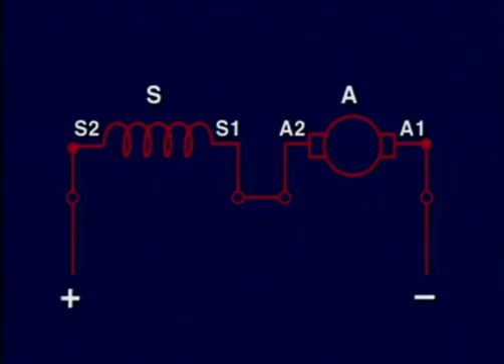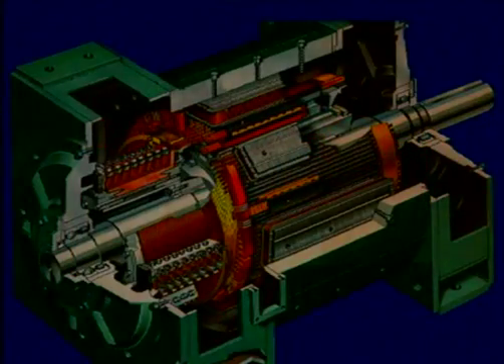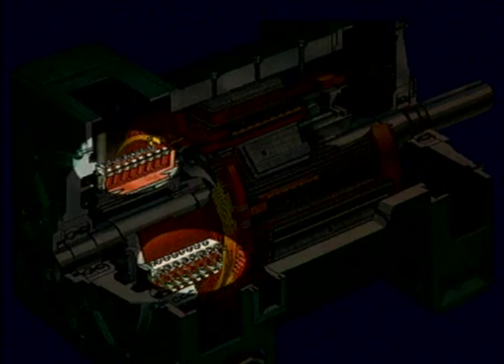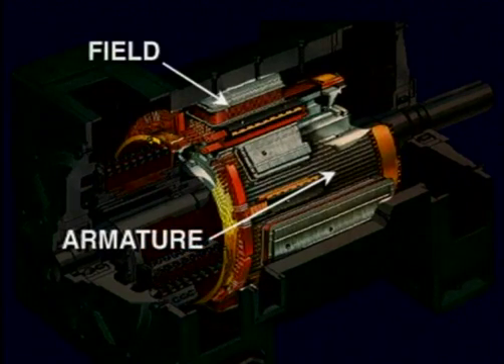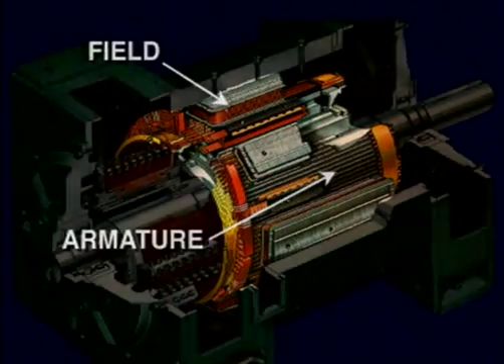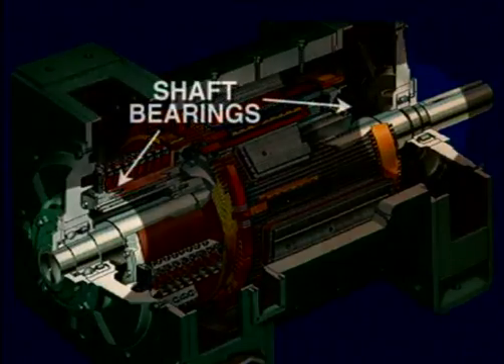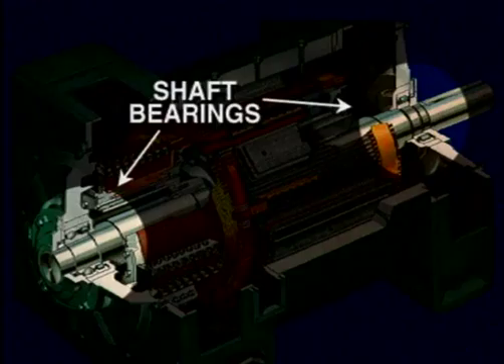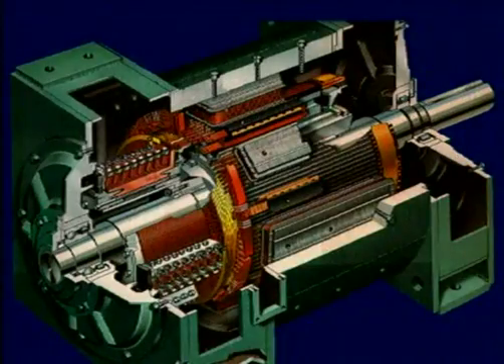One of the first things to check is to inspect the brushes to make sure they are properly seated and are not damaged. You can also inspect to see if the field and armature windings are loose or damaged, and check the shaft bearings to make sure they are lubricated and not damaged. If not properly lubricated, the bearing could be seizing on the shaft and create friction, which develops heat and reduces its capability to pull the load.